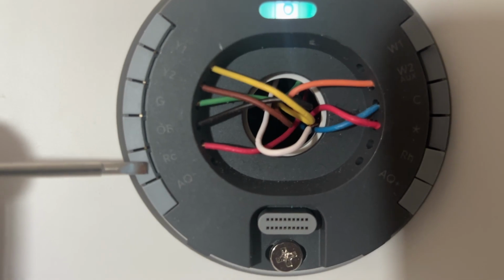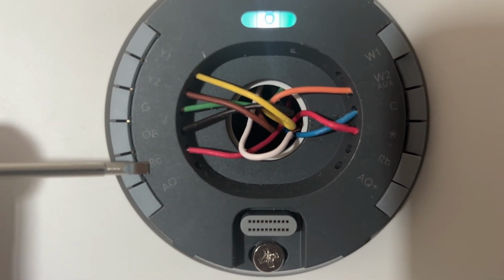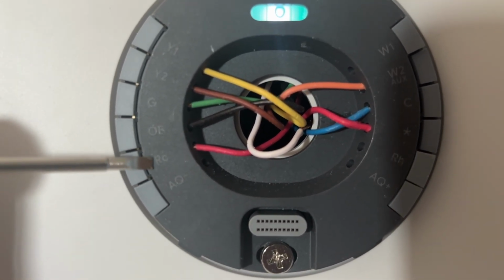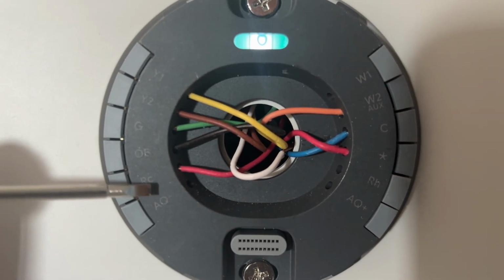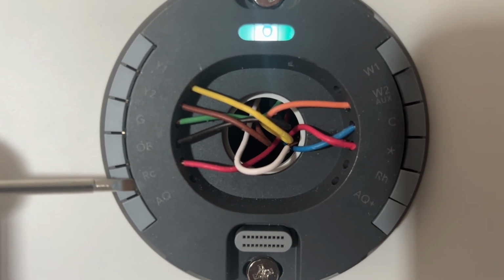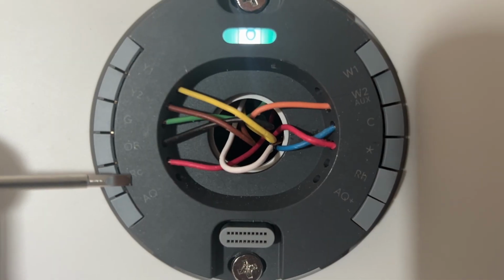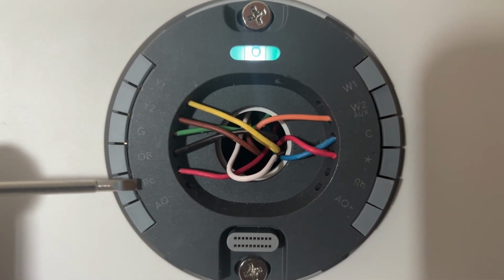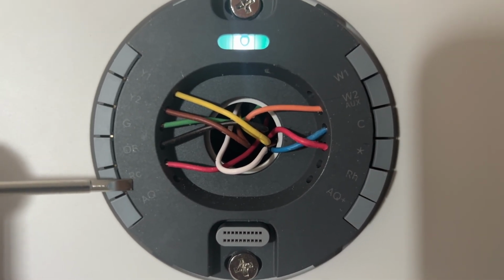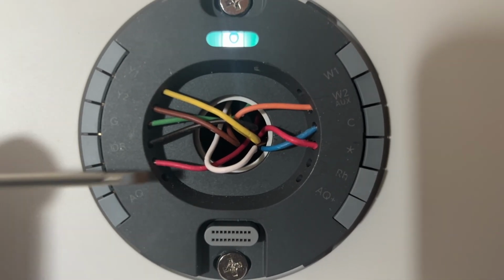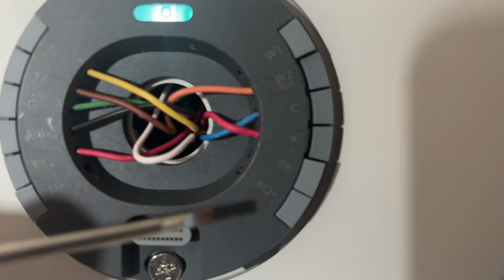The thermostat will know if you only have it hooked into one or the other that it's a single transformer. So we have elected to use RC, so it knows, hey, we're a single transformer, both heating and cooling, and is going to get its power from here. And no jumper wire is needed because it does it internally into the thermostat.